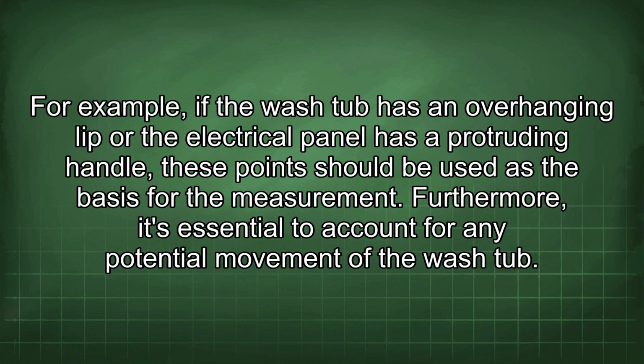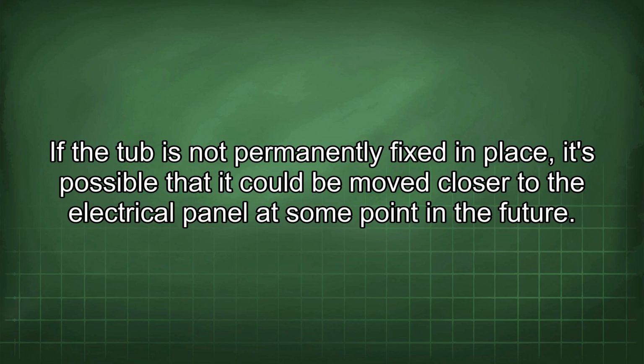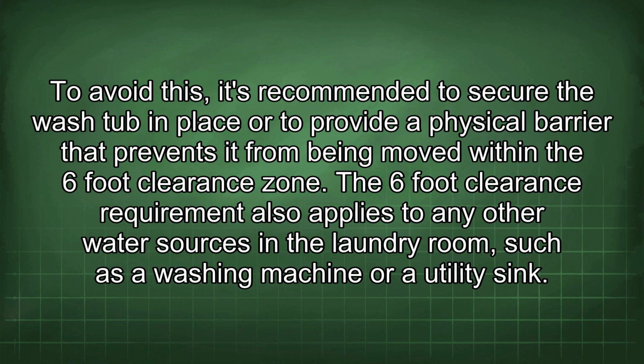Furthermore, it's essential to account for any potential movement of the wash tub. If the tub is not permanently fixed in place, it's possible that it could be moved closer to the electrical panel at some point in the future. To avoid this, it's recommended to secure the wash tub in place or to provide a physical barrier that prevents it from being moved within the 6-foot clearance zone.